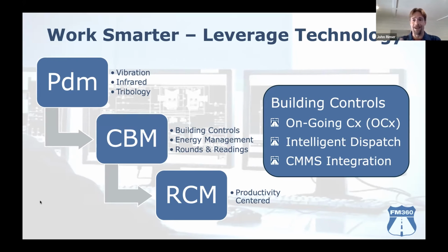So if we go outside a certain range, easy example, you're doing the delta P, the pressure drop across your filter bank on your air handler. Well, if that's a parameter I'm not monitoring through my building controls, then let's make sure we're capturing it on our rounds and readings, and it goes into the CMMS. Once it goes beyond that pressure change threshold, it says, hey, time to change the filters. That's a simple CBM we can do.